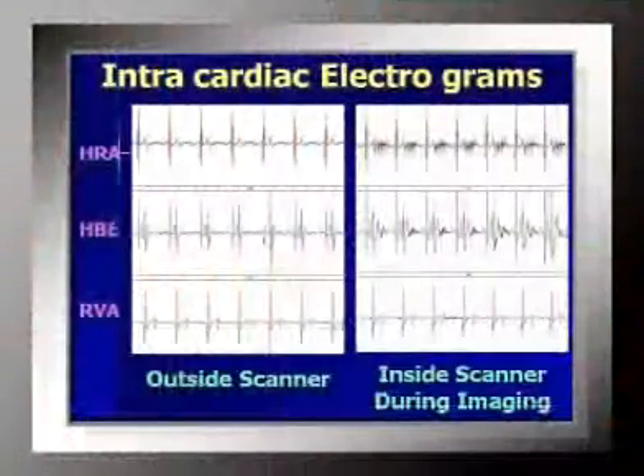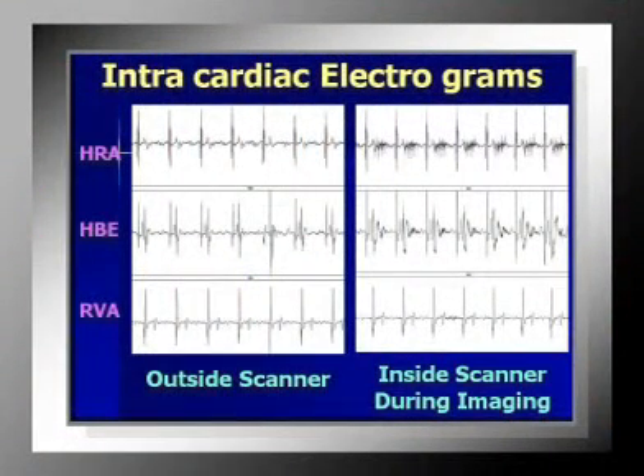So in the right atrial signal, we see this extra noise that occurs. This is actually from the gradient fields, which are needed in order to produce the images. But this particular tracing doesn't have any filtering in order to get rid of this gradient noise. These other channels have increasing levels of filtering, and the right ventricular signal actually has our best filters for getting rid of all the extra noise produced by the MRI scanner.